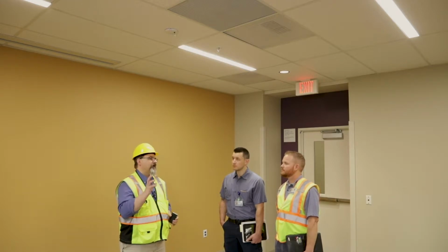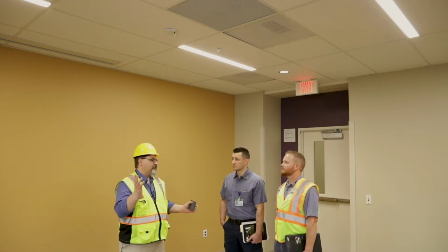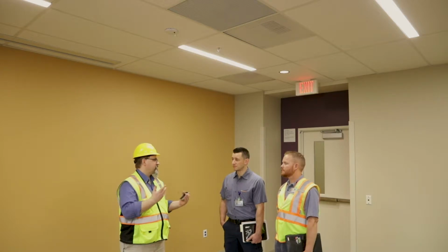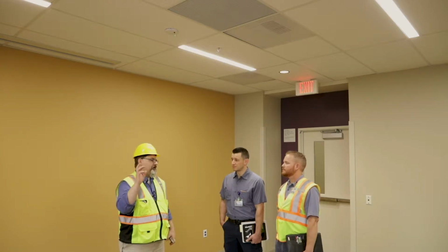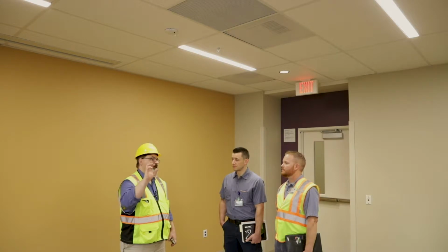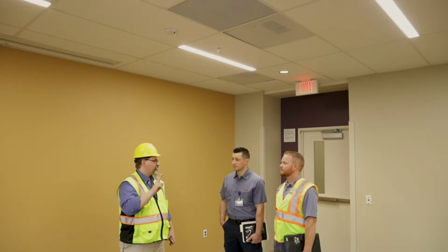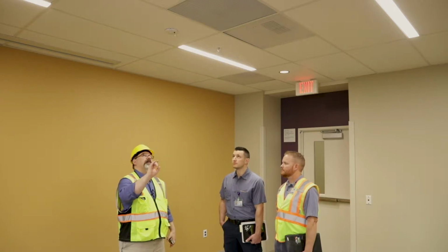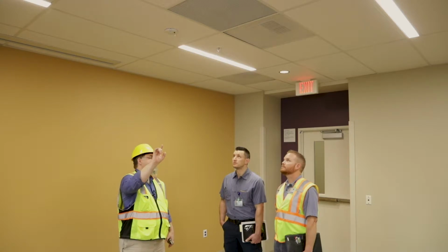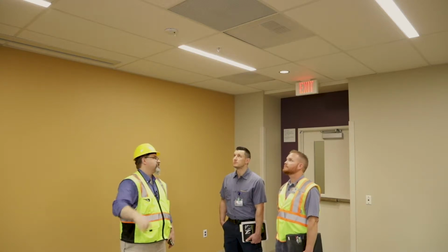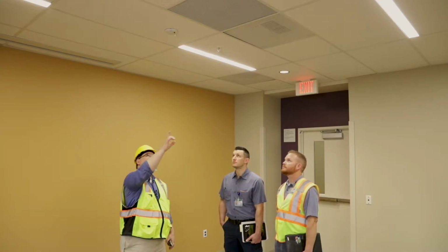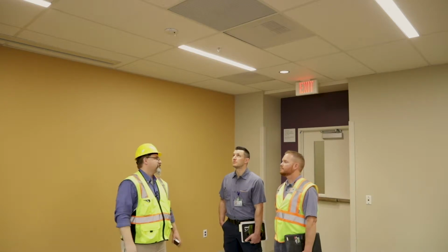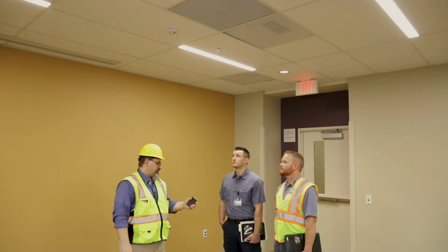Typically though, when you walk into a space, there could be issues with the sensors, and that's why I'm telling you this. When you walk into a space, both of the dual technologies have to trigger so that you have a turn on event for the room. The blue light is the ultrasonic, and those are the little speaker looking things on the side there. There's a transceiver there as well, that black patch speaks to this guy, so I can test a room. It's fairly easy to test a room.